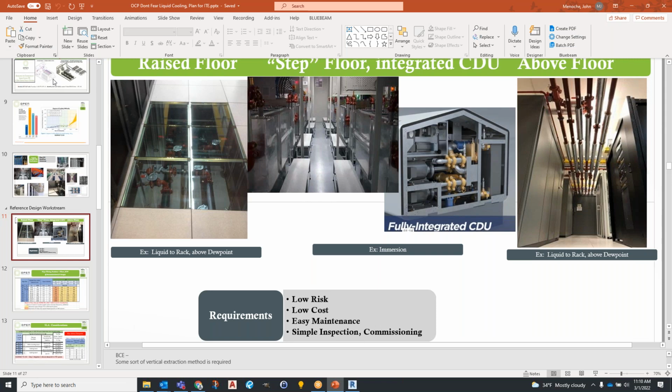So it's the height of the tank plus the overhead clearance required to pull a server out of the tank with whatever rigging is required. Any kind of drip pans or service racks that are required underneath for that process. What is the actual maximum height that's required?